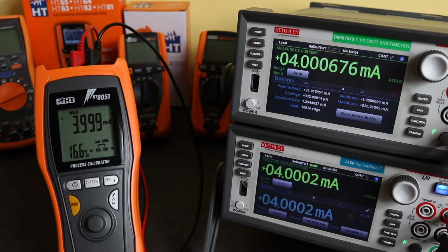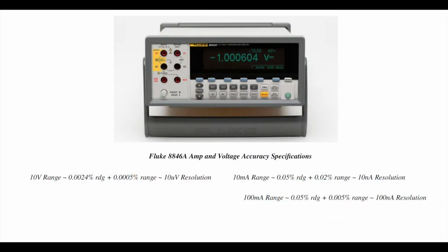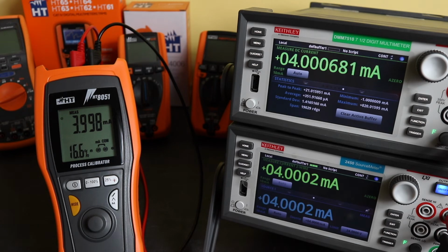And even if I look at my big Fluke 8846A that is currently in bits trying to be repaired, in terms of the amps, on the 10 milliamp and the 100 milliamp range, you have 0.05%, but you have plus or minus 0.02% of the range for the 10 milliamp and plus or minus 0.005% on the 100 milliamp range. So even that can't match the current capabilities of the HT8051. In terms of voltage, the 10 volt range, it can do 0.0024%. Plus or minus 0.0005% of the range. So in that respect, it can outperform the HT8051. And that's at its 1 year calibrations. Even on its 90-day calibrations, the current still can't outperform the HT8051.